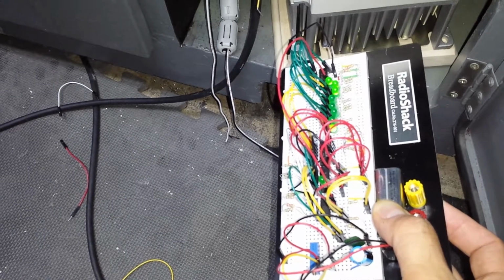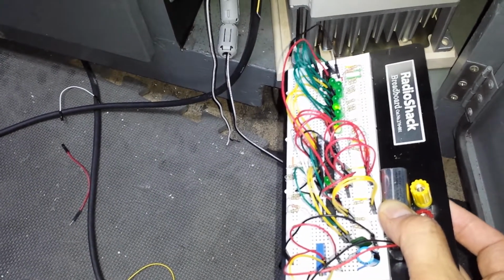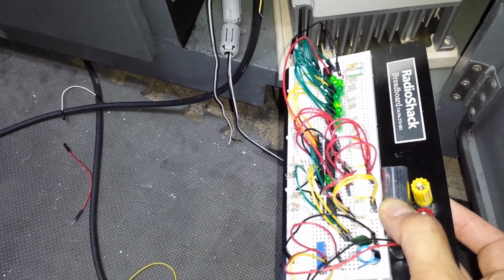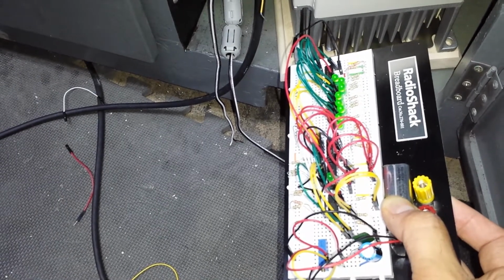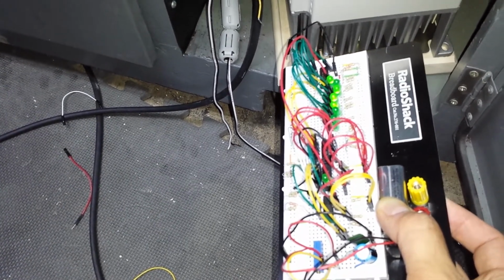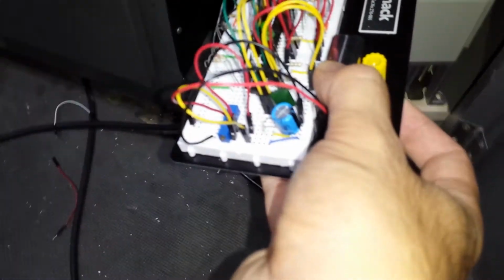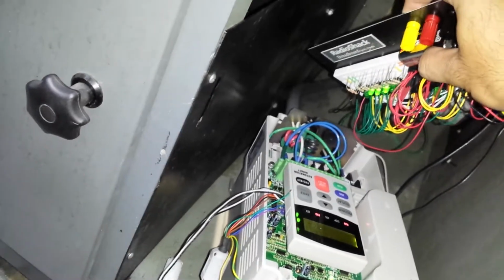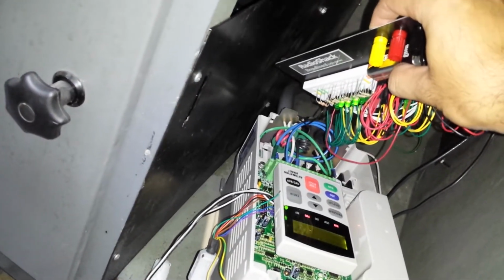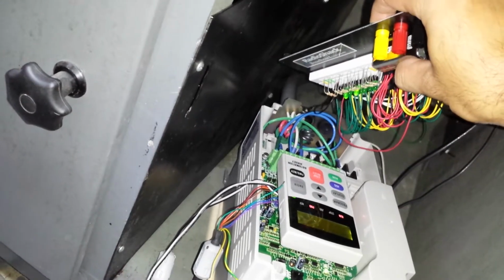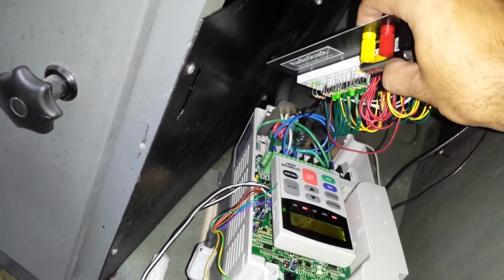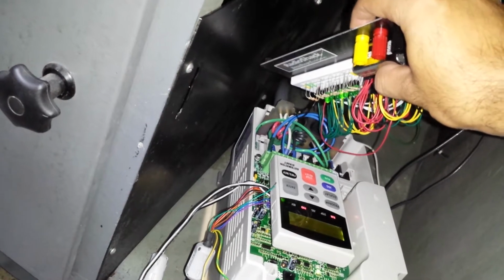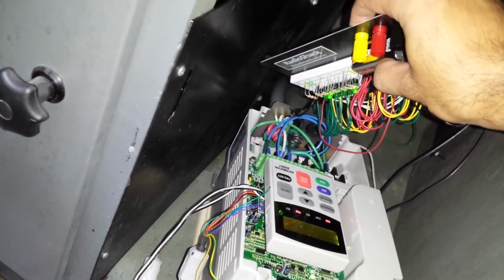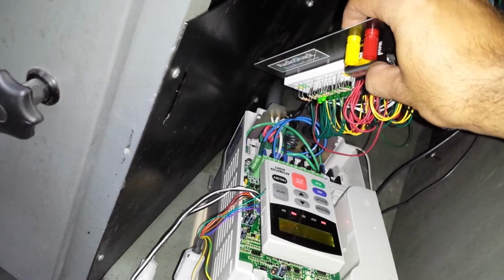I can get that wire about half an inch away from the VFD before it starts freaking out. And it's different for different areas of the VFD. If I put it on the power cables going to the motor, it certainly does it, but I have some ferrite cores wrapped around it now, so probably not as bad as it was before.